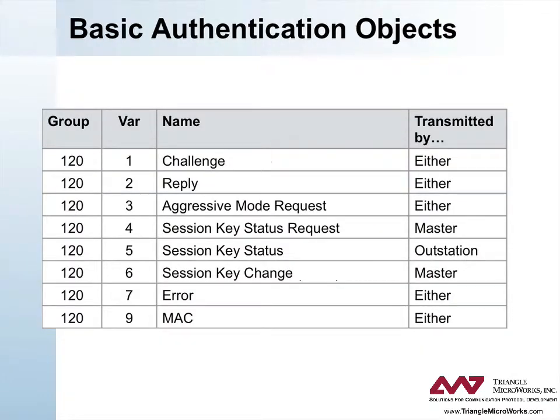There are eight new objects defined for use with basic authentication. All objects except those related to key exchange can be sent by either the master or the outstation. A challenge message is sent by a receiver to indicate that the previously transmitted message must be authenticated. The challenger supplies data to be included in the authentication calculation. A reply message contains the MAC used to authenticate a message. An aggressive mode request and a MAC object, HMAC or GMAC, are included at the start and end of a DNP3 fragment respectively, to authenticate a message without exchanging a challenge and reply.